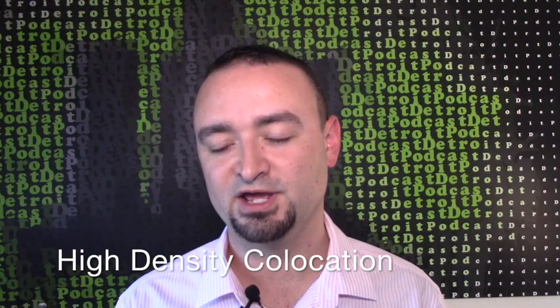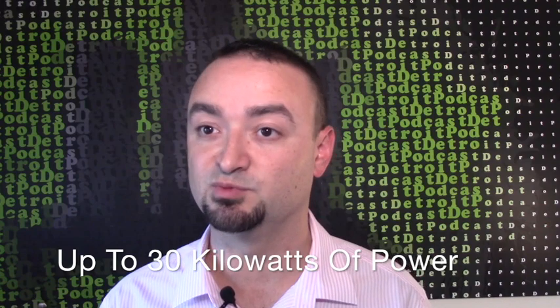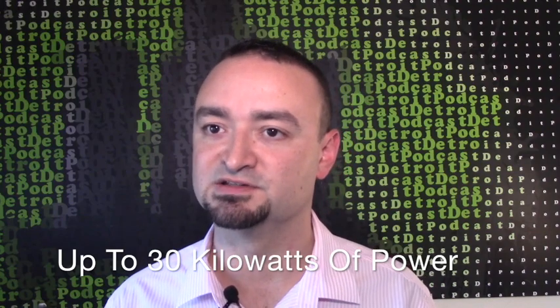Okay, so what is high density colocation? Why don't you define that for the audience? So high density colocation is when, say, a cabinet will be using a certain amount of power, which in the old days would be somewhere between 1 to 2 kW of power. Today I would average that at probably closer to 10 to 12. But in a lot of these high dense clusters today, we're seeing up to 30 kW per cabinet. And so that's the amount of power draw. That's really how I would classify high density.